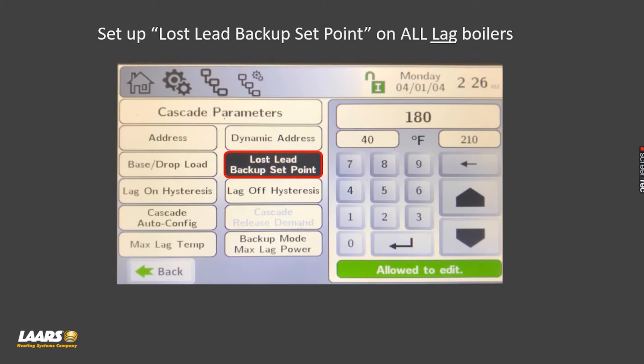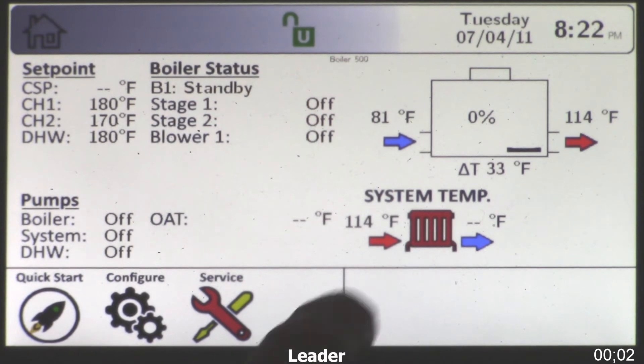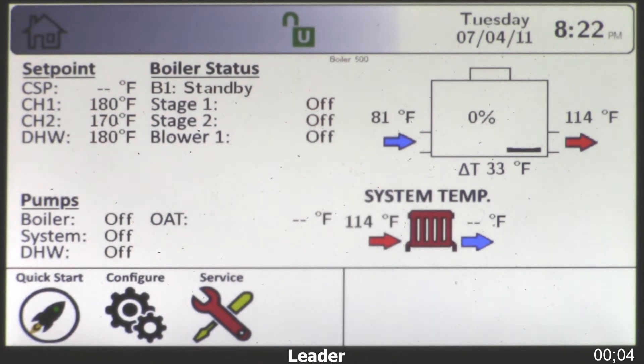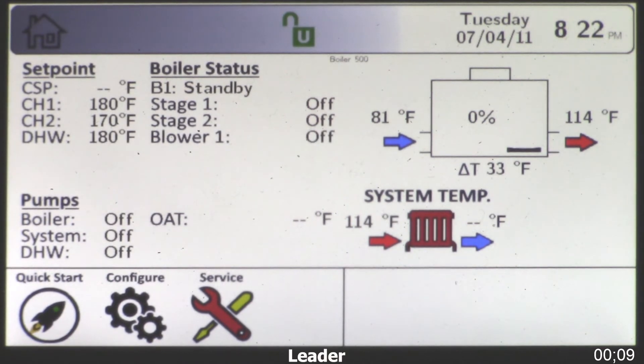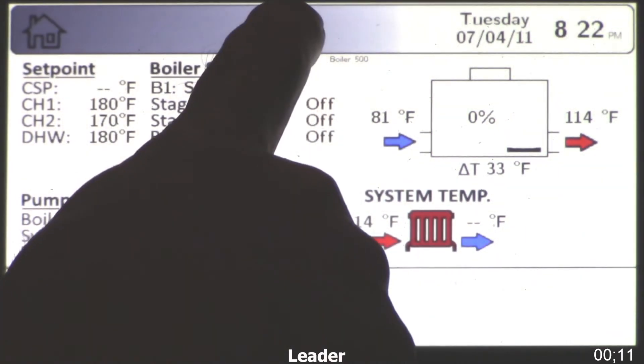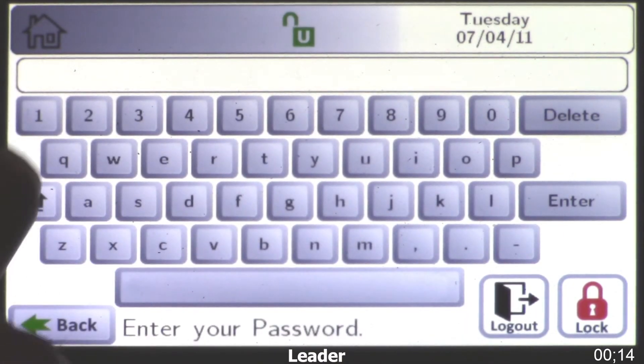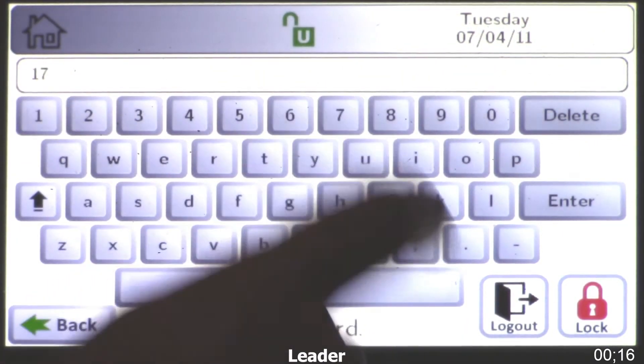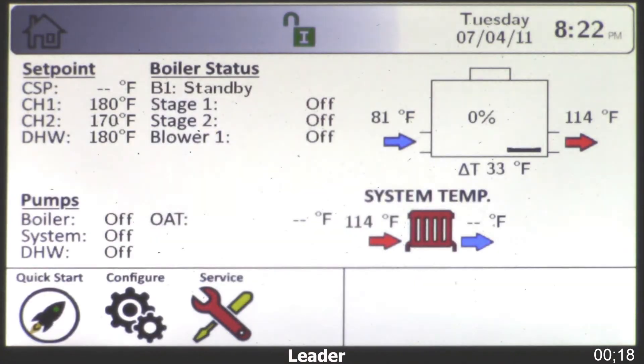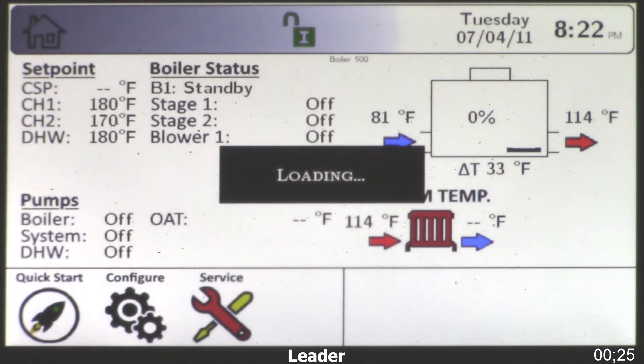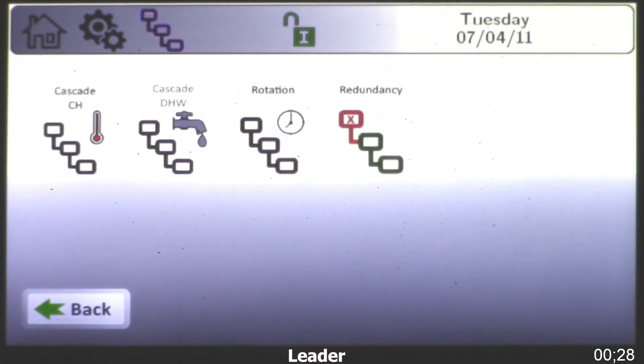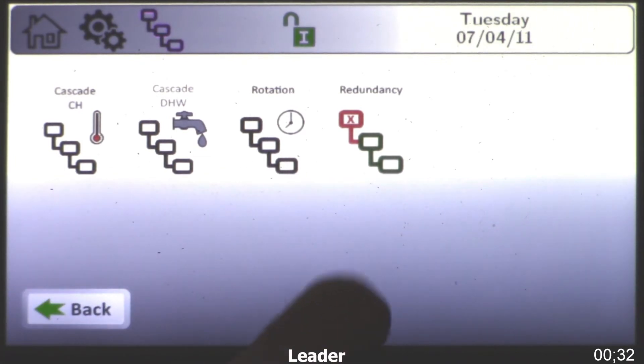Now we'll play a video. Your lead boiler should have the system sensor — once it's wired in, you'll see that on the home screen. All the boilers in the cascading bank will have to be logged in. Here I'm choosing the lead boiler and typing in 17, then enter. Now we have the installer password. Next we're going to go to configuration and choose cascade — you'll see your options here, including the redundancy setting I mentioned previously.